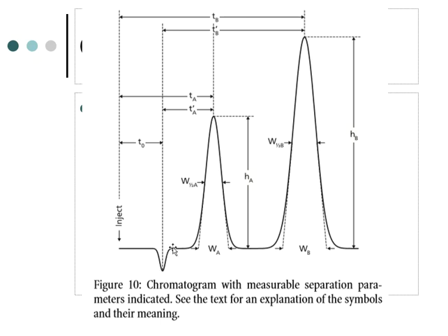And that water dip shows me that a sample is getting ready to come out. If I don't see that water dip, then there could be a problem. Maybe my instrument is not injecting sample at all. So here we see our first component come off. And then here at WB, we see our second component come off. We can talk about height. That's what the H is here, the height of A and the height of B.